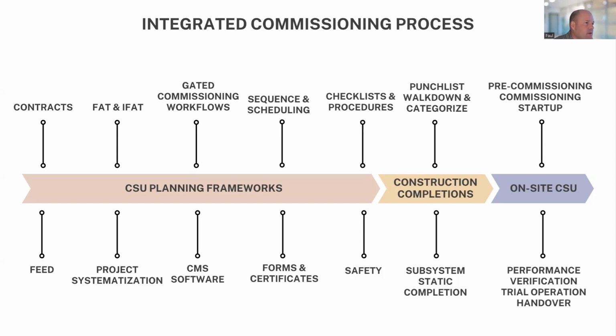That's probably answering your question, Taryn: how important are SAT and FAT to mitigating delays in commissioning? They are critical to mitigating delays. If we've properly defined FAT requirements in our contracts and what's tested off-site, that needs to align with what's tested on site during SAT, comparing results to make sure there's no damage during shipping or installation. On a lot of projects we see that they don't align - it's just left up to the manufacturer to test what they want in FAT. If you're testing something different, skipping things, or doing things differently, and FAT and SAT aren't lining up, you're already running into problems before you've really started.